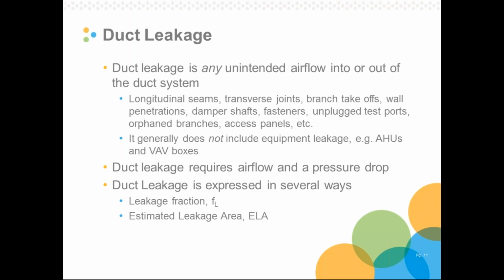That said, there's some basic requirements for duct leakage. It requires both an airflow and a pressure drop. Importantly, if you have a duct system that moves 1,000 CFM, you obviously have an upper limit for how much duct leakage there could be. The other side of that is the pressure drop. There's a difference of pressure inside a duct and outside a duct, and that is the driving force for the duct leakage. So the higher the pressure, the higher the leakage.